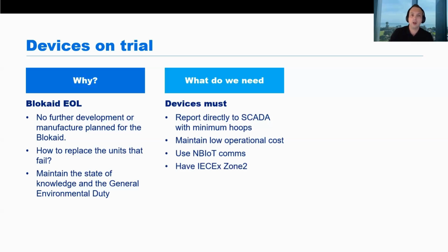We need the devices to have a Zone 2 explosive environment certification and maintain that, and we need to have reliable reads of levels of at least 5 meters. This is coming from the spread of the length of manholes we have on the network. And if we cover 5 meters, we're covering something like 93% of our manholes.